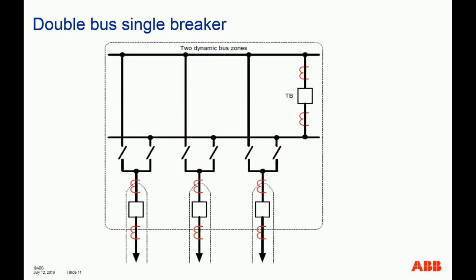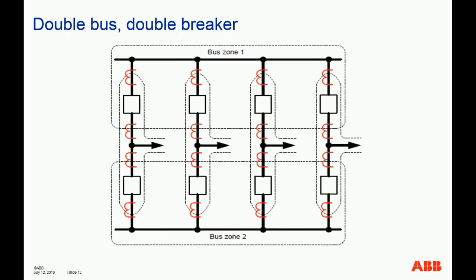Depends on the location of one of the two disconnect switches. For example, if this switch is closed, it's connected to bus A. If this switch is closed, it's bus B. So you need to have a certain type of dynamic zone allocation scheme.